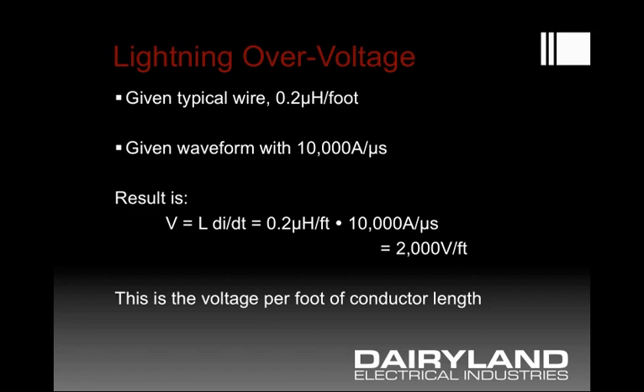Here's an example calculation showing the effect of conductor length and inductance. A typical wire might have an inductance of approximately 0.2 microhenries per foot. Looking at a lightning waveform with a rate of rise of current of 10,000 amps per microsecond, the resulting calculation shows that you can have several thousand volts per foot of conductor length.